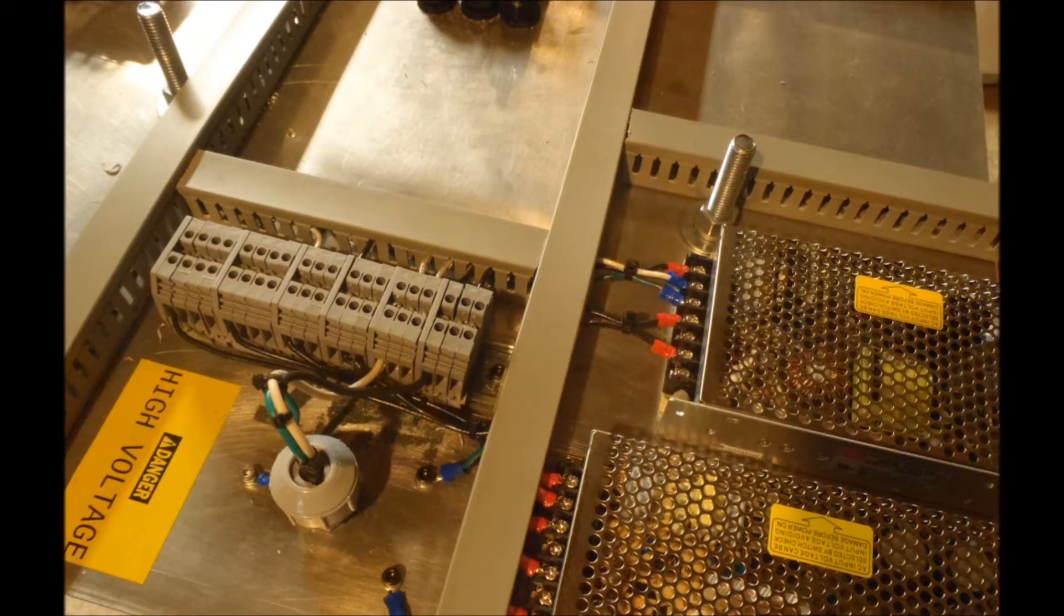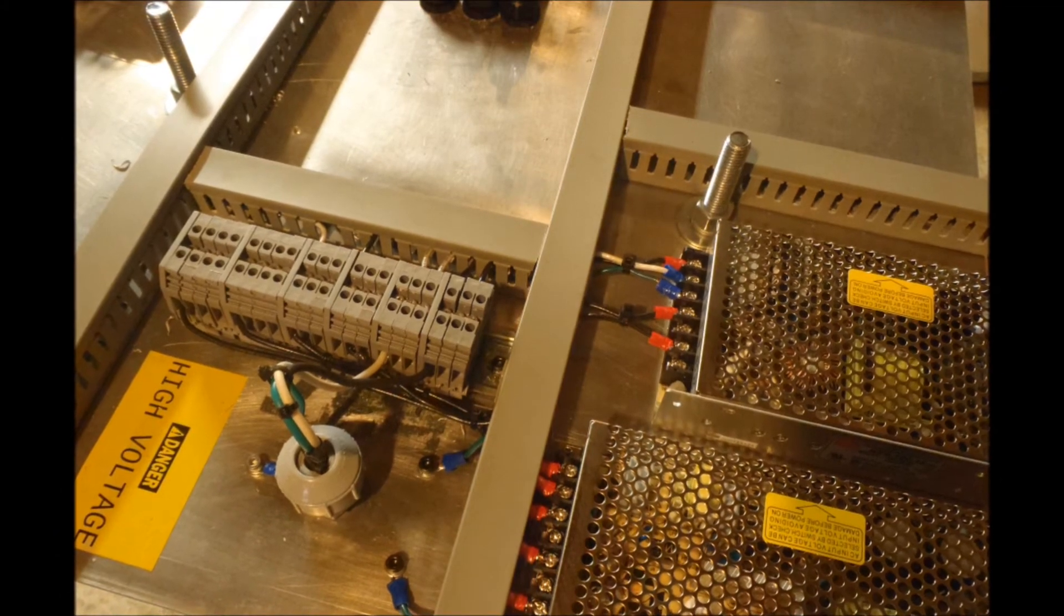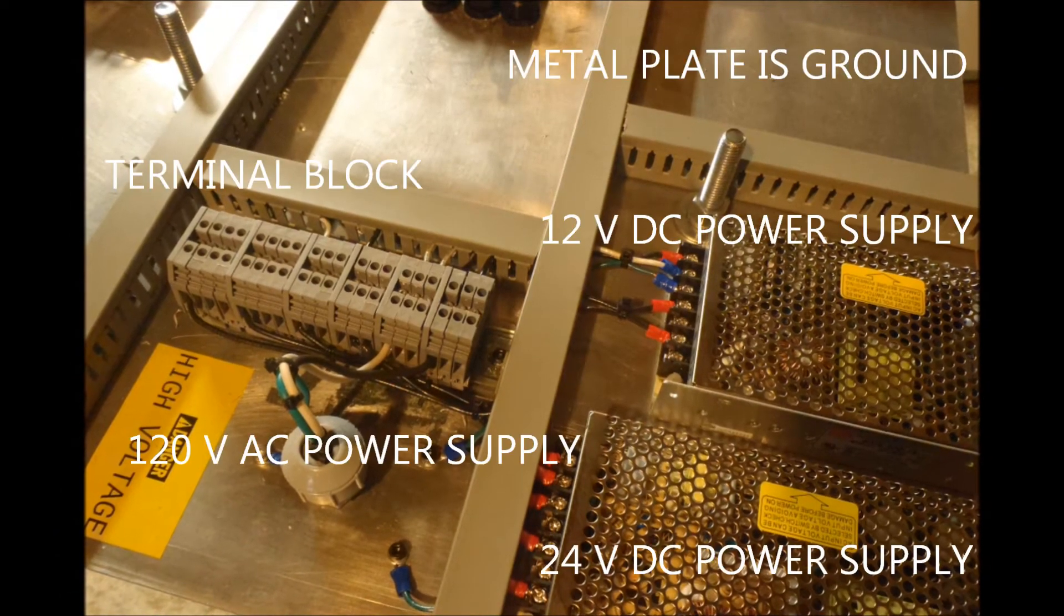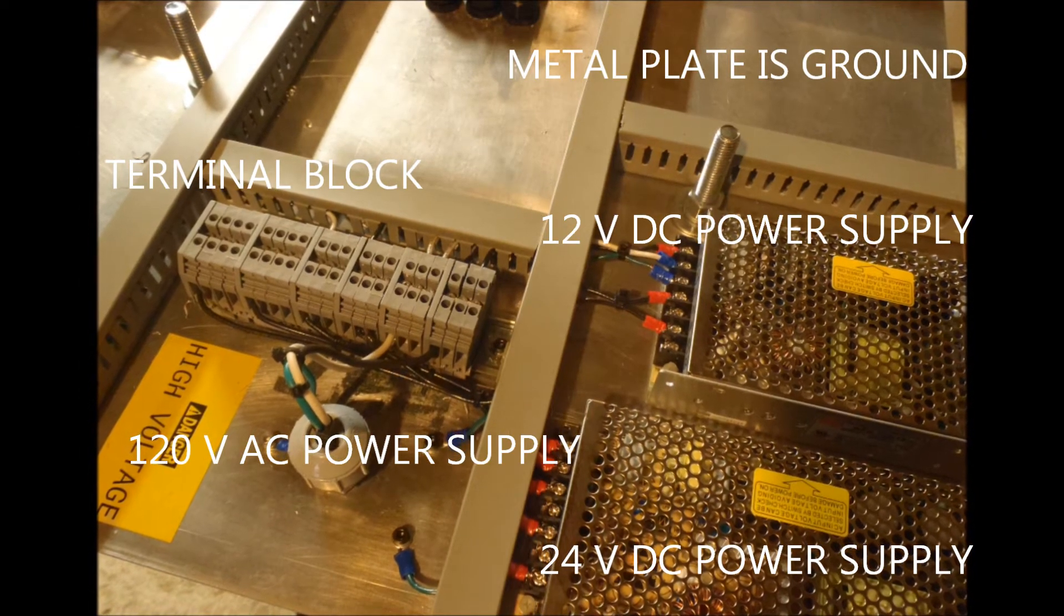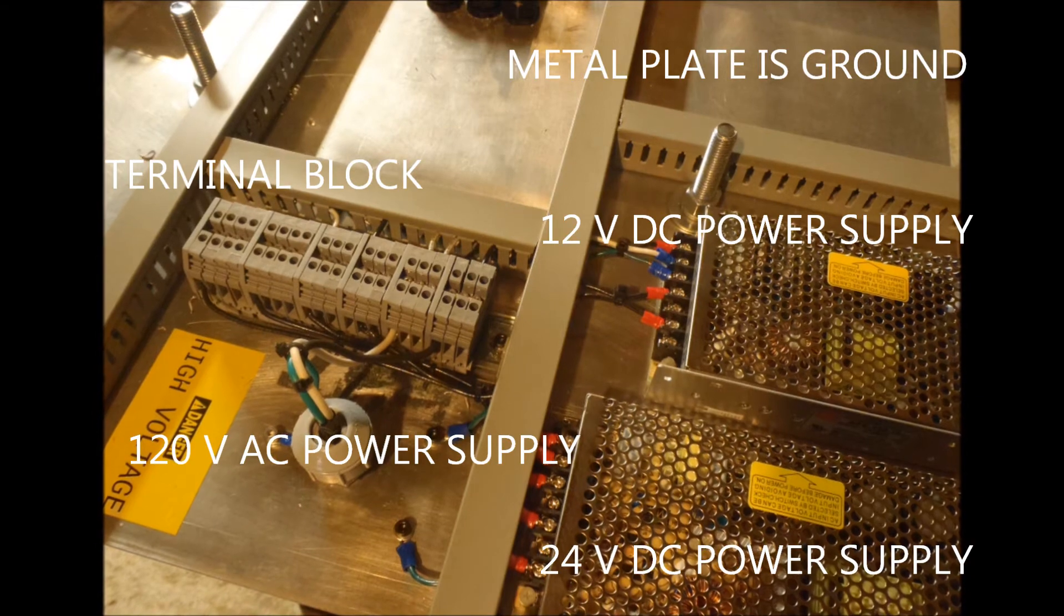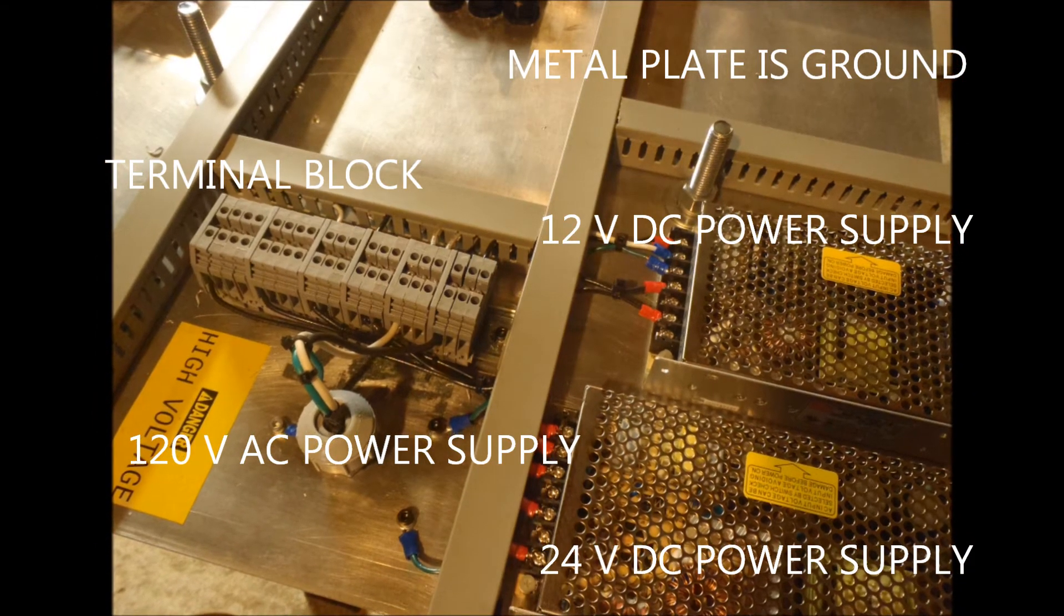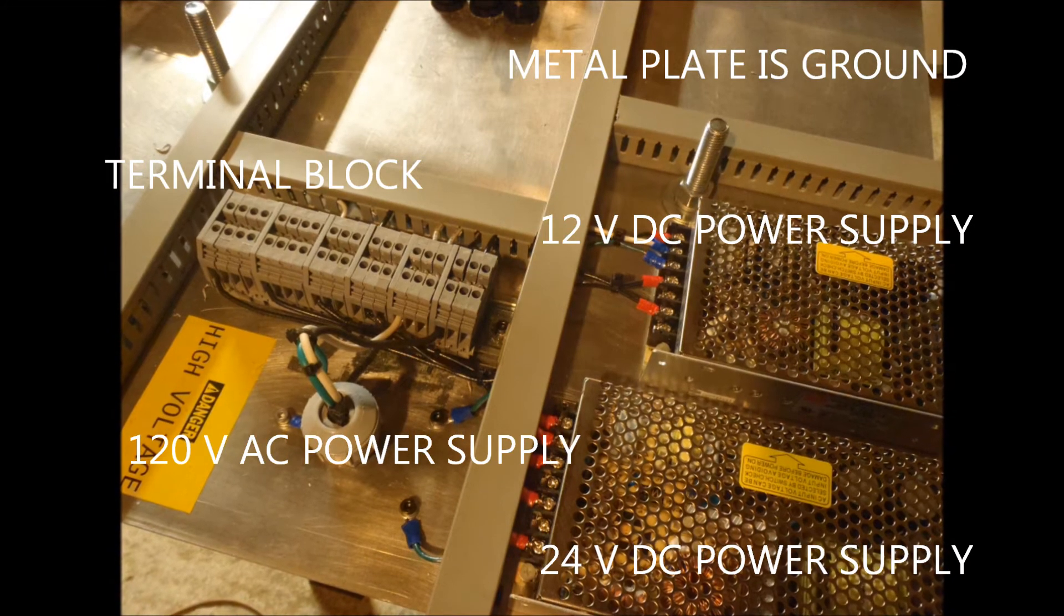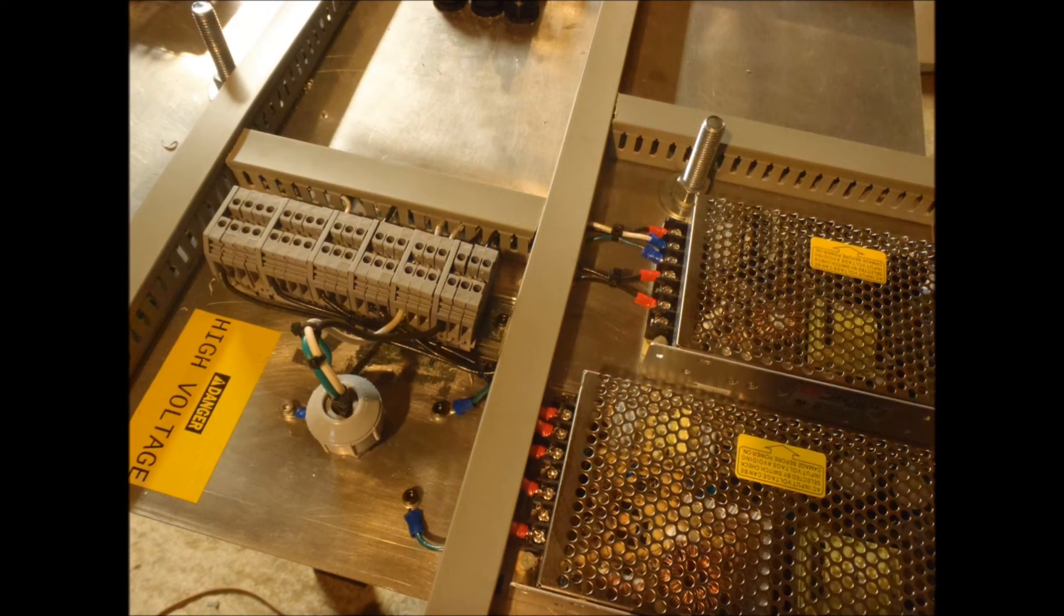As you can see, here are the voltages in the system: 120V, 12V, and 24V. The larger power supply is the 24 volt, the smaller one is 12V, and 120V is directly mounted onto the terminal blocks. Both DC power supplies distribute back to the terminal blocks, and all the wiring is kept neat with Panduit.